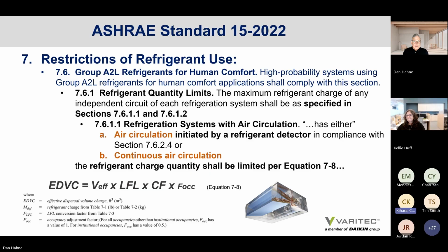I've done a lot of selections, and the pounds per 1,000 cubic feet that you actually exceed, you comply by a lot. So the whole system would probably have more charge released to the zone as opposed to VRV with stop valves. Correct. Okay. Because in a heat pump system, if you don't have any SSOVs, you have to take into account the whole entire charge of the system.